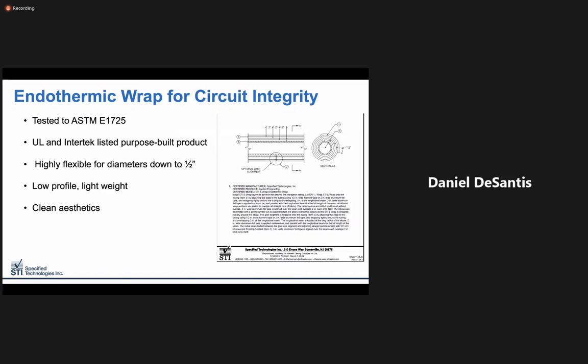Here's a little summary of what we've learned about endothermic wrap so far. It's tested to the industry standard for circuit integrity in ASTM E1725. Third-party testing from UL and Intertek labs with unique listing numbers for various applications. The product is highly flexible for use in small diameter conduit or threaded rod supports. At just half an inch thick per layer, it's thin. And at just 1.3 pounds per square foot, it's the lightest weight solution on the market today. No additional support for weight is required. And of course, EWRAP gives the design professional a clean aesthetic for exposed ceiling and open concept designs.